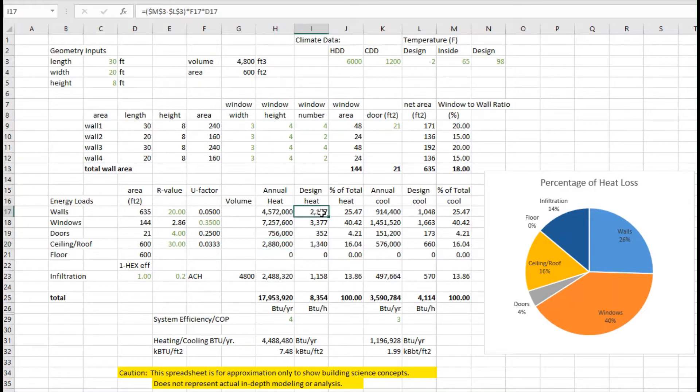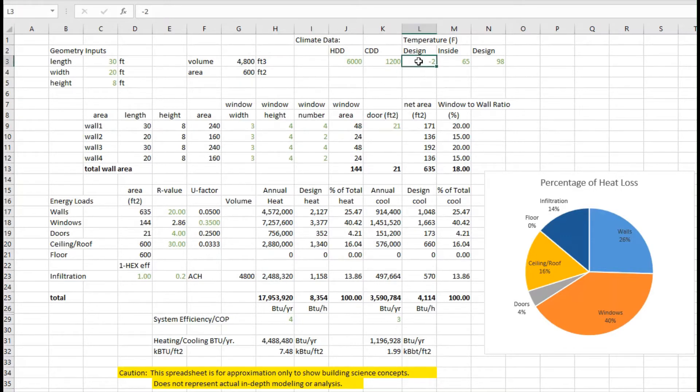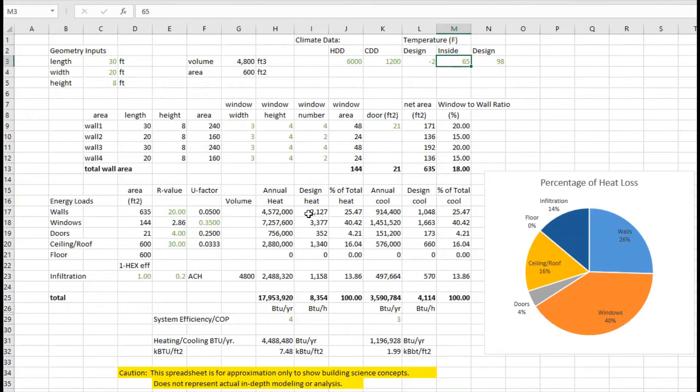We can also calculate - it's kind of a very simplistic model - but based on an outside design temperature, perhaps the coldest day is minus two degrees Fahrenheit, and inside we're trying to keep it at 65. I can calculate what that design heat load is in BTUs per hour.